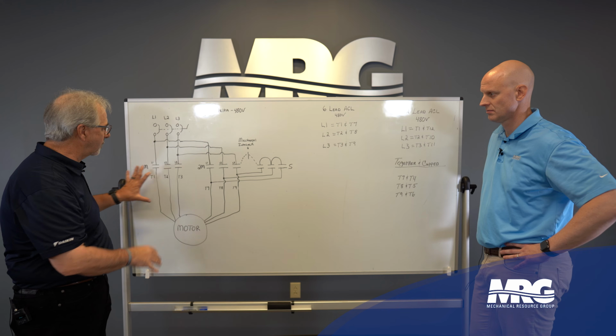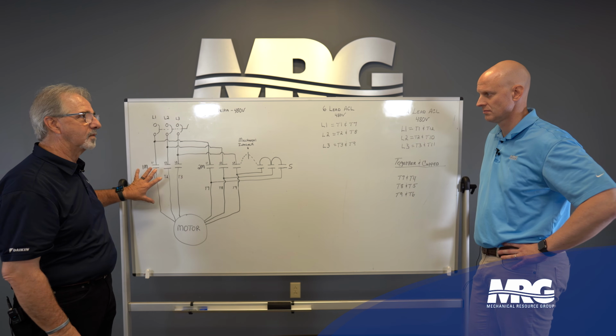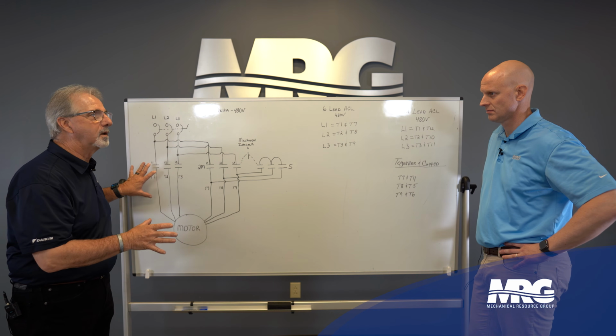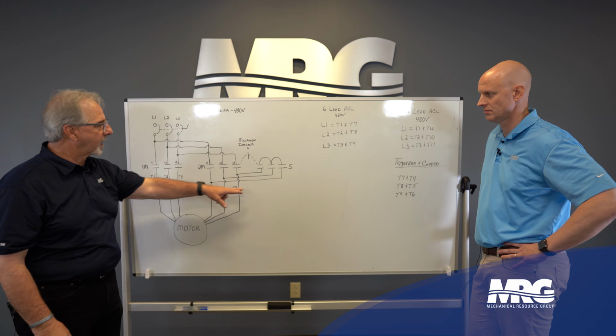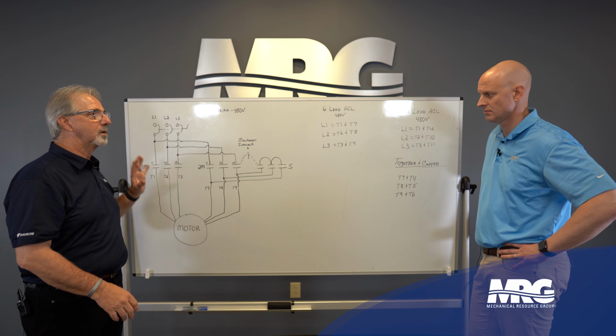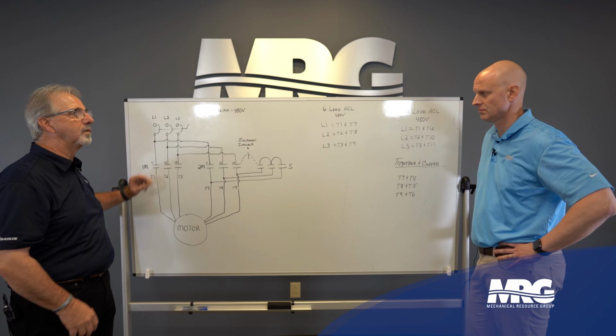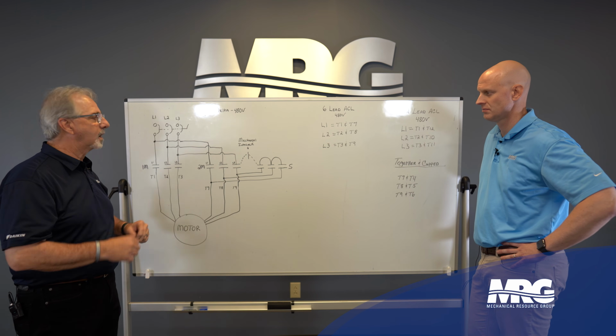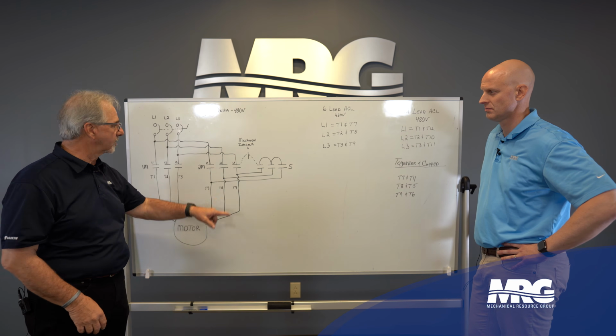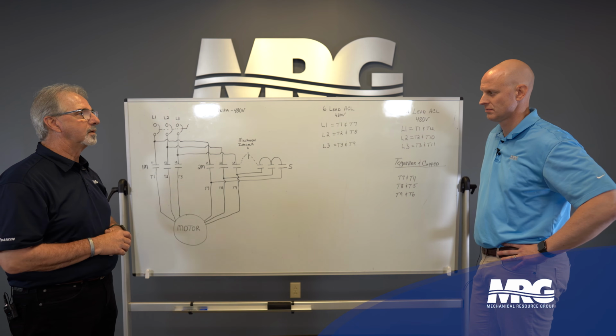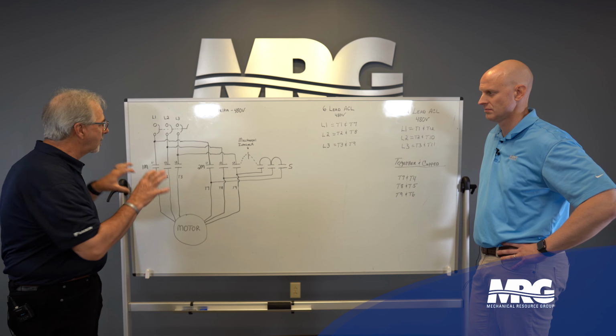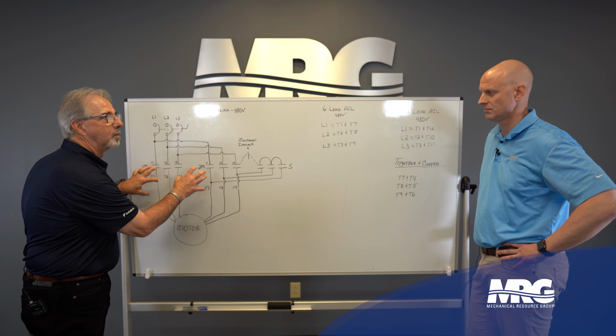So we are in sequence, and my polarity is the same inside there because I don't have to use half the winding, okay? So what I do is I short out the Delta during startup. I only use this portion of it, and it runs a little bit. Timer times out, drops the shorting contactor out, and brings in the 2M contactor. When I am in running condition, both these contactors are in at one time.